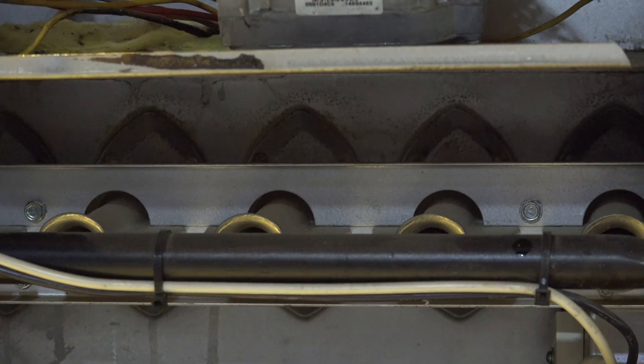And obviously you can see there — we had a rollout of flame when we had less back pressure from the inducer. So that's it on that one, just another heat exchanger problem on a gas furnace.